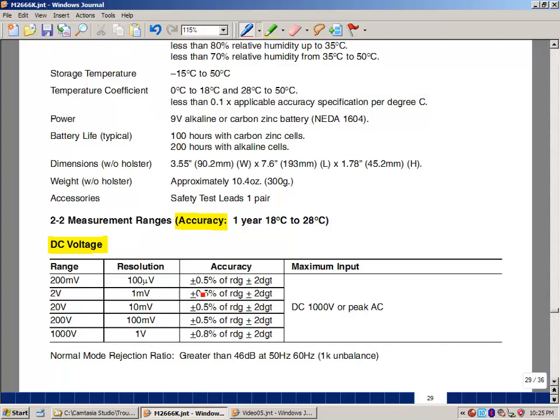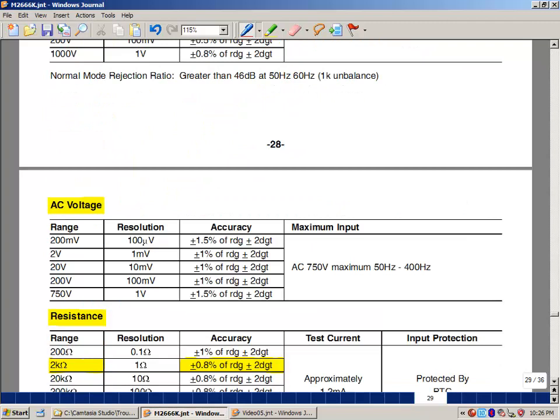Specified here is a percentage of the reading on the display, also a quantizing digit error. We'll explain this in just a little bit. You have similar types of things specified and some of the accuracy changes depending on which setting we are on the meter.